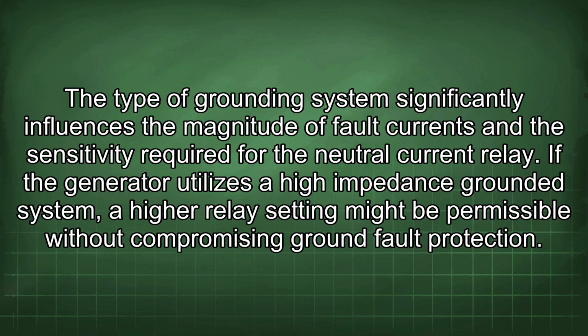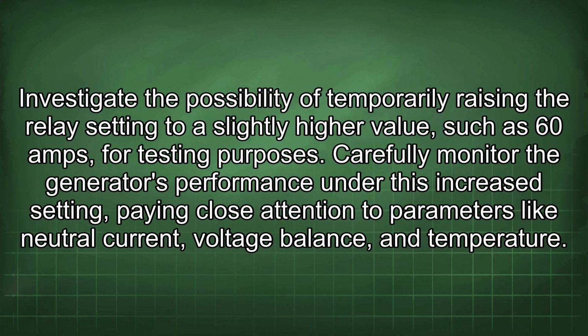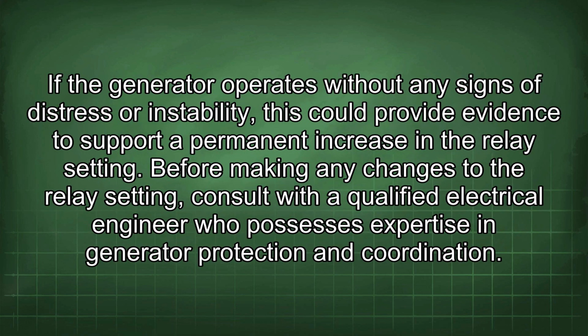Investigate the possibility of temporarily raising the relay setting to a slightly higher value, such as 60 amps, for testing purposes. Carefully monitor the generator's performance under this increased setting, paying close attention to parameters like neutral current, voltage balance, and temperature. If the generator operates without any signs of distress or instability, this could provide evidence to support a permanent increase in the relay setting.